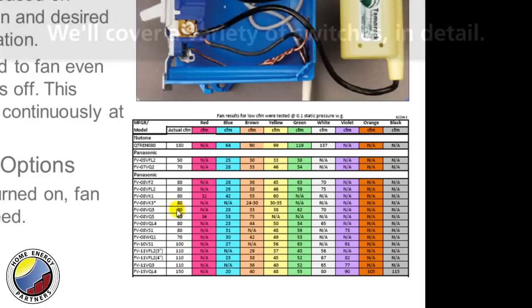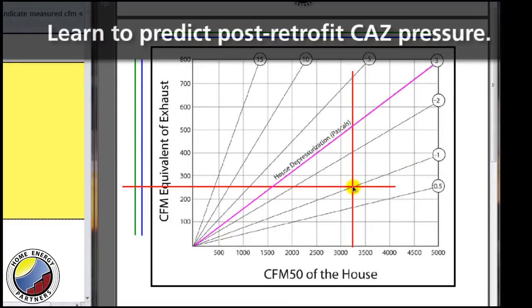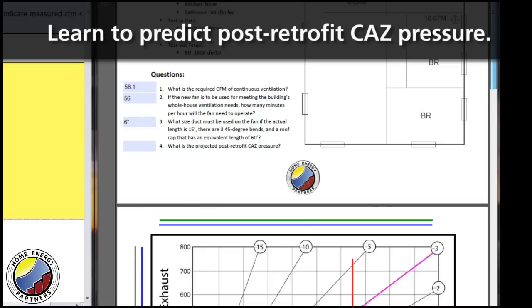I found where those two intersected and I put my horizontal line, and we know that when that test scenario was done that had a CAZ pressure of negative one, I was only exhausting 10 CFM out of the bathroom.